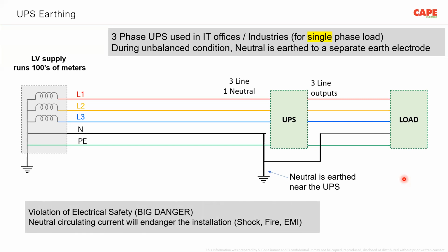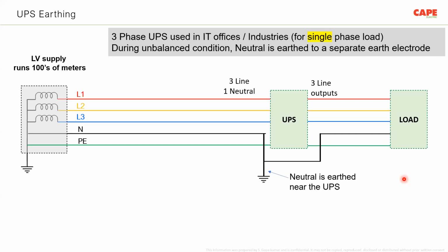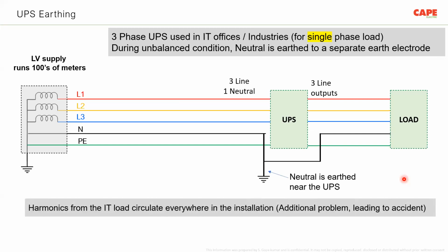Actually, this is a total violation of electrical safety requirements, and it's really a big danger. Neutral current will circulate everywhere within the installation. It will flow through every metallic part of your building, and it will create shock, fire, and electromagnetic interference. So this kind of wiring is absolutely wrong. In addition, harmonics is another bigger issue. People start using modern devices to reduce or nullify the neutral current, and a lot of exercises are going on. But the very simple subject which you should understand is that this is a violation of electrical safety requirements.